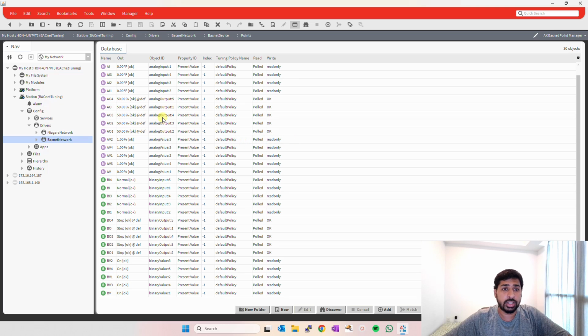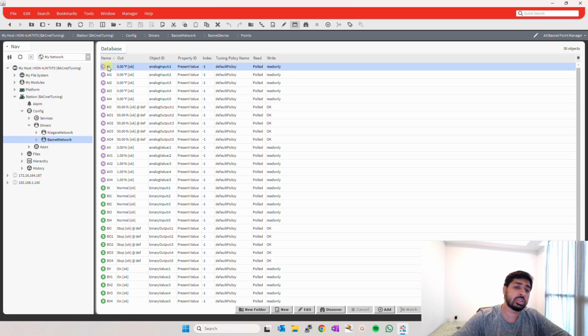Now, what is recommended in this scenario is that you have analog inputs, analog outputs, analog values, binary inputs, binary outputs. Say in the analog inputs, you have temperature sensor, humidity sensor, pressure sensor. Analog outputs, you have your speed signal, which shows what the VFD is doing, what your valves are doing. And then there are analog values, which might be a few constants to run your PID, a few constants which you're using for your internal program, where there is no change as such.